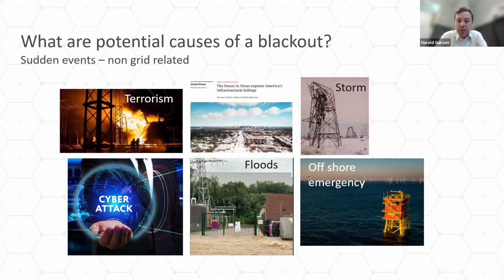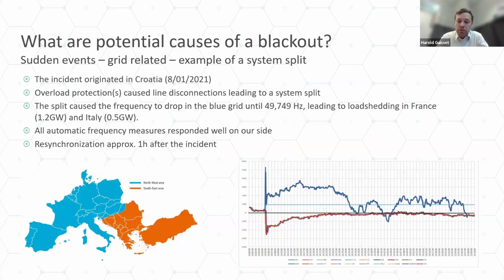Because as Pierre rightly said, we always operate the grid in an N-1 principle. So if a storm knocks down one line, it shouldn't be a problem. The grid should still be operable, and the population should not be affected. But if a storm, floods, or a terrorist attack are big enough, and they take down more than one line, more than one cable, this could really put the grid in jeopardy, and this could cause a blackout if there are enough of those events, just as Pierre mentioned. Those events, yes, we have emergency plans to work on the effect of those events, but it's not really possible to prepare for them.